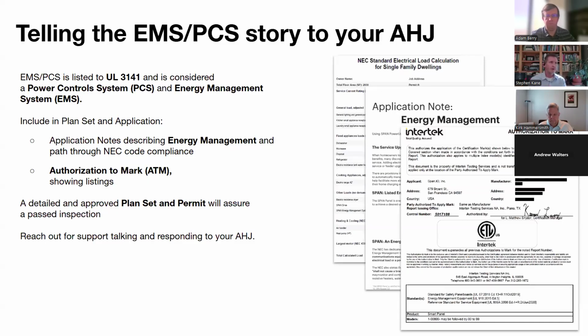So what does that look like through your permitting process? I would offer that it's really important that the products have the right listing. Again, 3141 being the one to kind of rule them all. Previously, we used UL 916, and we had some language in UL 1741 about PCS. But ultimately, these things should be included in your permit packs, and they should be listed on the equipment so that the inspectors, as classically they would, utilize UL listings as the way to comply with code requirements. That's ultimately the way that it is smoothest in the field.